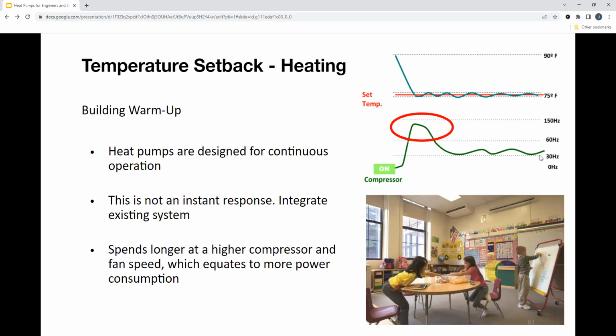After 5 p.m., 6 p.m., hey, it doesn't make sense to heat the building to 75 degrees or 72 degrees. Let's set it back to 65 degrees, right? And I've heard some building owners do this, and then they start to realize that their energy bills are going way up. And you could probably guess that the reason for that is this is where we don't want to be. And with an hour building warm-up, right, we're going to spend a lot longer time with your higher compressor speeds. Fans are going to be running at full volume just to make sure we meet this temperature. So this right here is what we're trying to avoid.